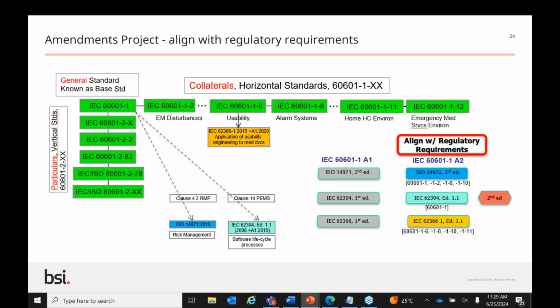As a convention going forward, A1 will mean Amendment 1 and A2 will mean Amendment 2. And you can see on the right-hand side by the rectangles near the bottom, I use A1 and A2. There was a desire to align regulatory requirements to ensure that SC62A updated to the most recent versions of standards that are referenced in the 601 series of standards. Since ISO 14971, third edition, and you can see in the blue, that's the third edition on the right side of the slide, which is the medical device risk management standard has been updated to the 2019 version. All references throughout the general standard and applicable collaterals now reference 14971 third edition or 2019. And if you look just below the blue rectangle, you'll see the reference to the applicable general standard and collaterals.